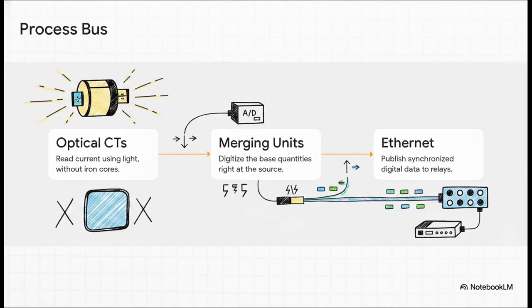The real game changer here is the IEC 61850 process bus architecture. Step 1, you replace those heavy iron core CTs with next-gen optical CTs that literally use light to measure current. No iron core means zero saturation. Step 2, devices called merging units, or MUs, sit out in the yard and digitize these base quantities right at the source.